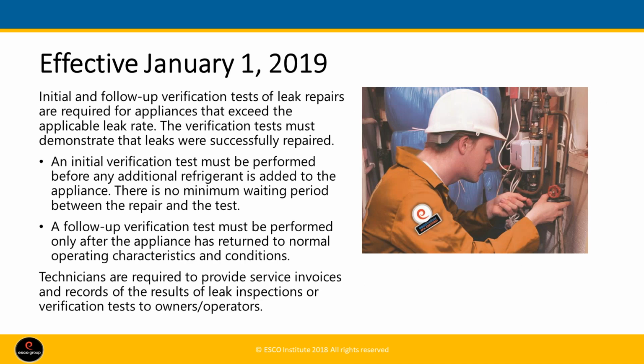Initial and follow-up verification tests of leak repairs are required when the appliance exceeds the applicable leak rate. These tests must be performed before any refrigerant is added to the appliance in an operating condition.